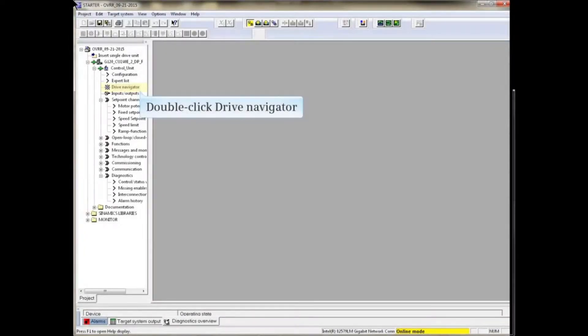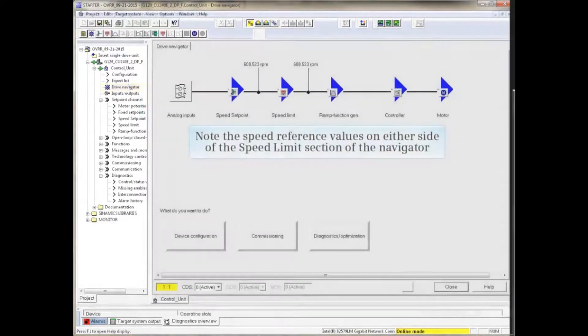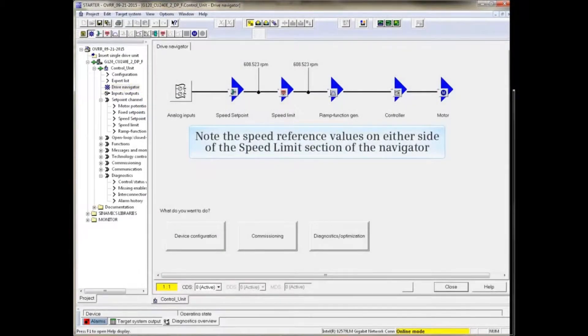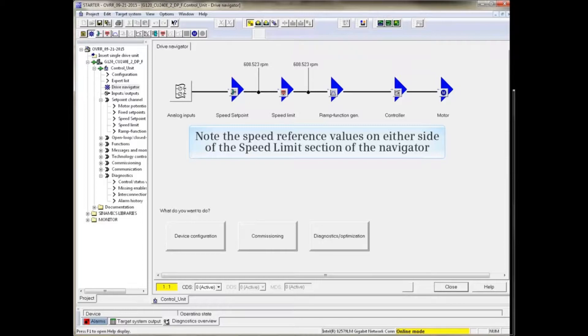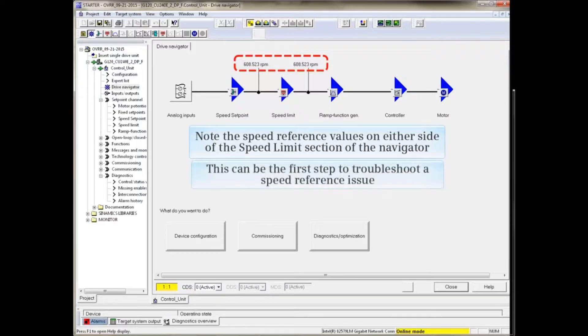Double-click Drive Navigator from the project tree in Starter. The Drive Navigator window opens. If you are online with Starter, note the speed reference values on either side of the speed limit section of the navigator. This can be the first step to troubleshoot a speed reference issue.